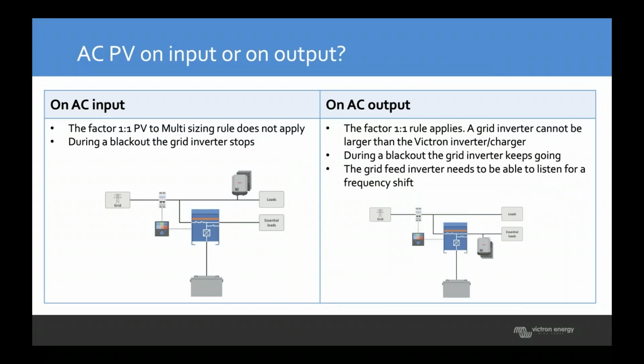The other thing we mentioned: AC PV on the input or the output. On the input, you don't need to follow that one-to-one sizing rule, but during a blackout, the inverter stops, and the AC PV Fronius stops. On the output, the one-to-one rule does apply, but during a blackout, the inverter will keep going. In this arrangement, you need to have the frequency shift set up.